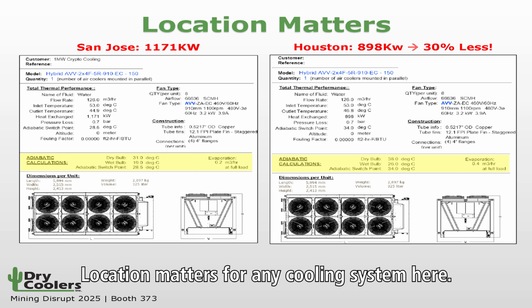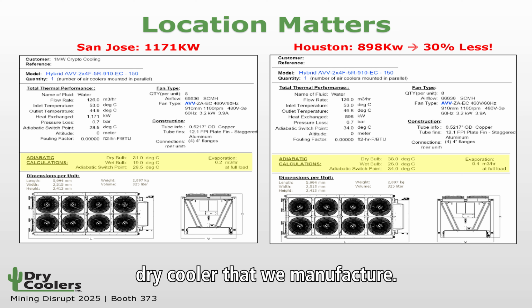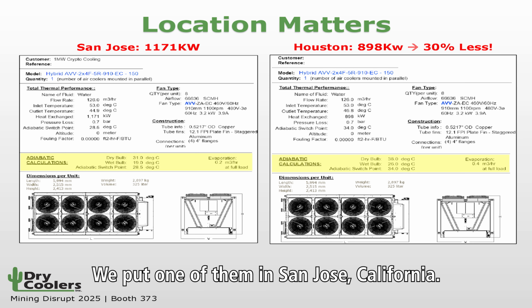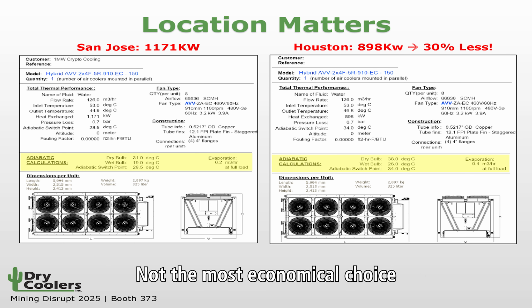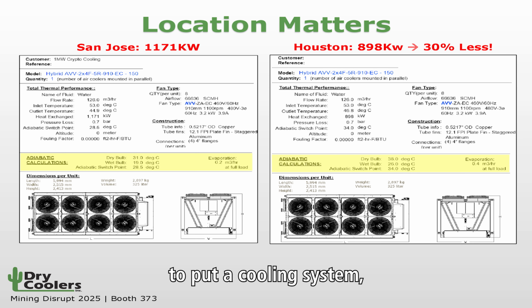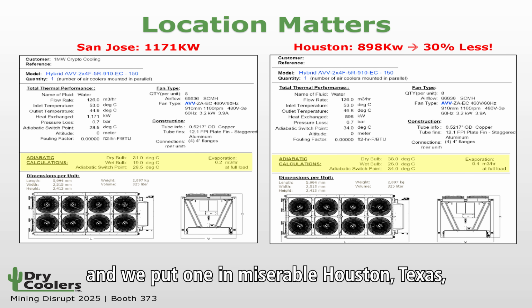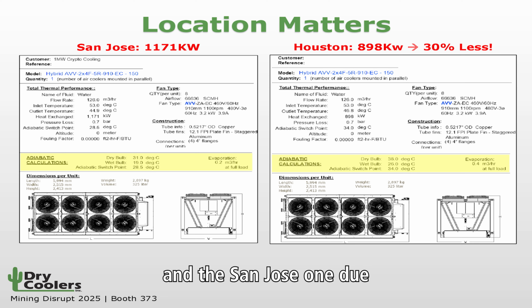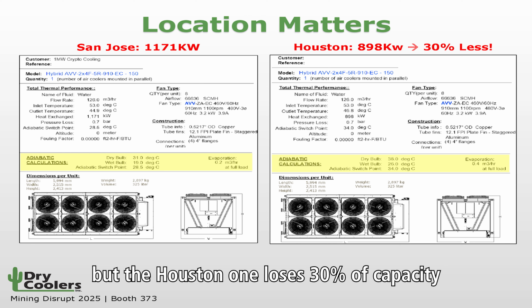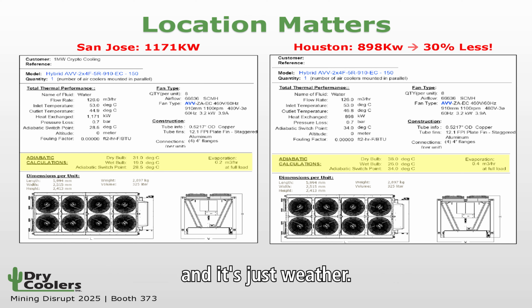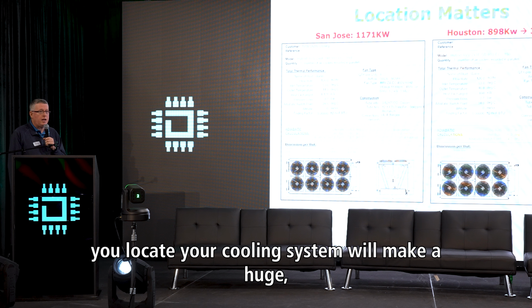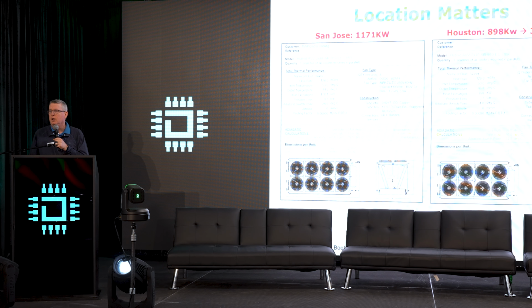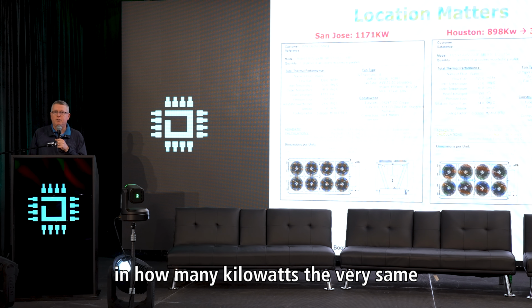Location matters for any cooling system. Here we took the same 8-fan dry cooler that we manufacture. We put one in San Jose, California, not the most economical choice to put a cooling system, and we put one in miserable Houston, Texas. The San Jose one, due to its low summer temperatures, kicks butt. The Houston one loses 30% of capacity, and that's just weather. So where you locate your cooling system makes a huge difference in how many kilowatts the very same cooling system can remove. I vote for Saskatchewan for you guys—nice and cool there.